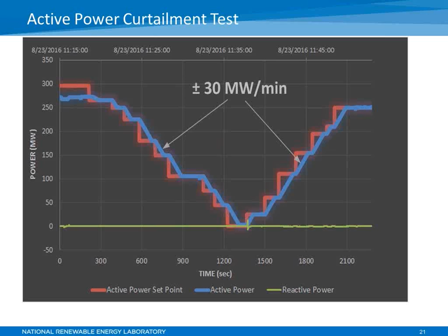Another important thing to notice is that the plant can provide non-spinning reserve as well, not just spinning reserve. In fact, in a PV plant, unlike any conventional generation, there is no differentiation between spinning and non-spinning reserve capacity, due to the nature of PV generation as an inverter-coupled resource. So you can see here that the plant follows the active power set point very accurately, and it's tracking very accurately its 10% of rated capacity per minute limit.